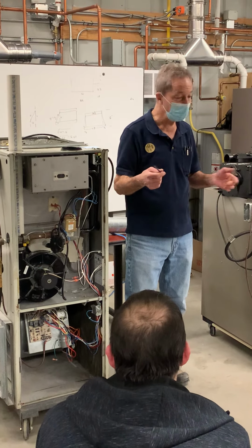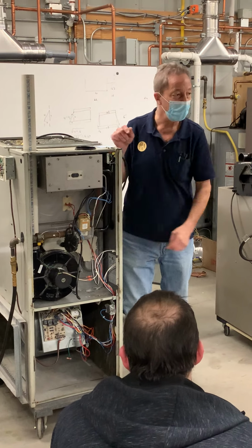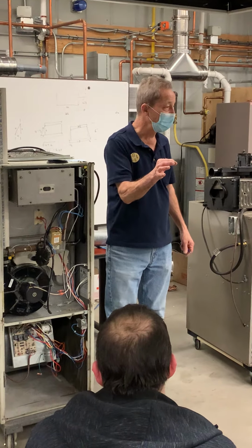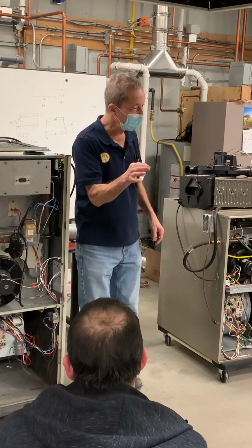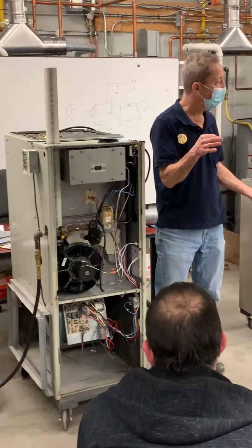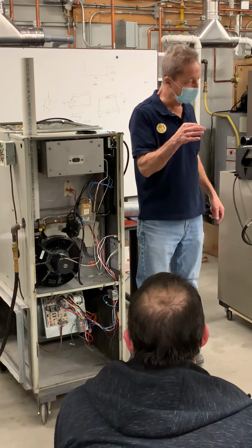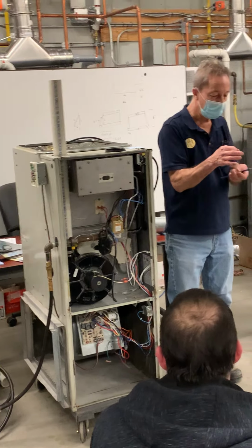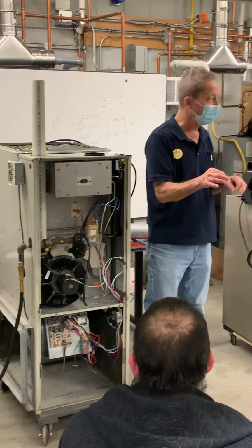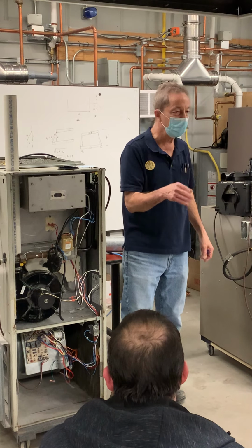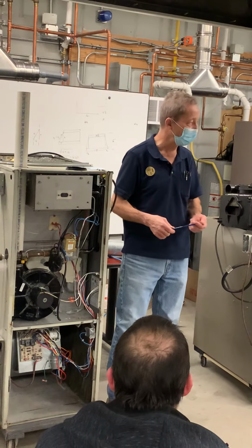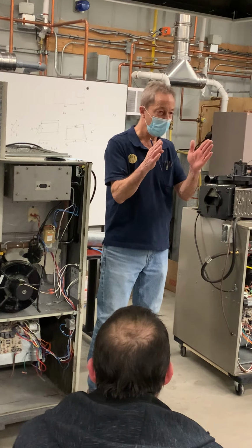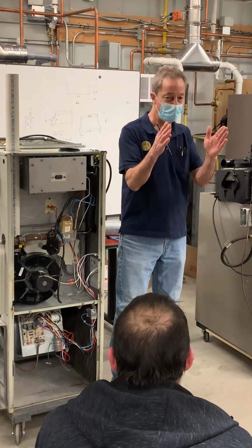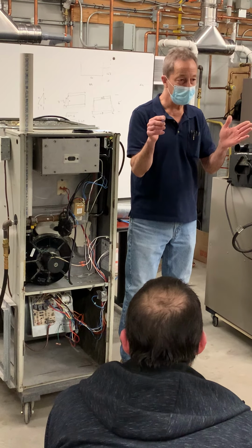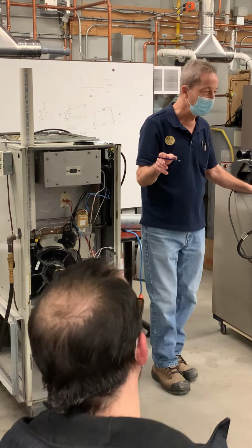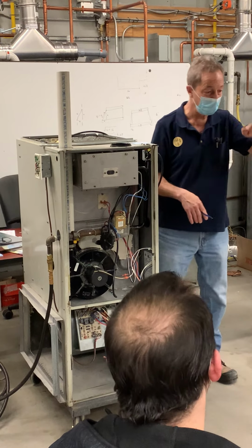So with that in mind, that hose going back to here goes to the back side of the regulator on the gas valve. So if I've got it set for 3.5 with the cover off, and then I put the cover on, and it goes to -1, that hose will suck back on the back end of the diaphragm, overcome a little bit of the spring pressure, and automatically reset the manifold pressure to 2.5. Now I've got my 3.5 differential between manifold and the burner environment. Remind me next week, we're going to hook up a digital manometer on here, we're going to fire it, I'm going to block the intake, and we'll watch the manifold pressure change.